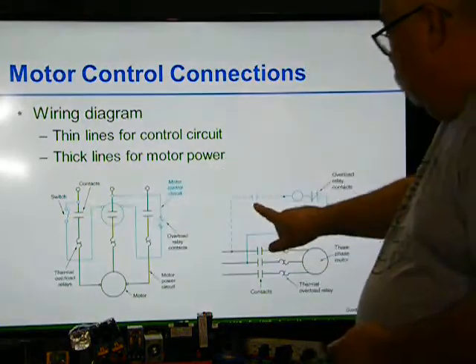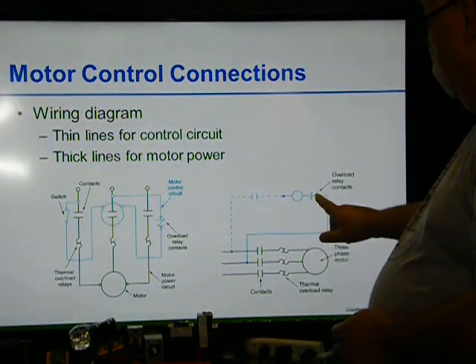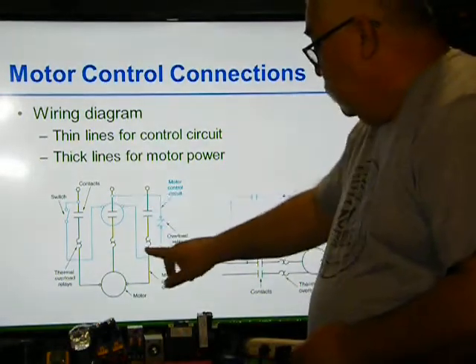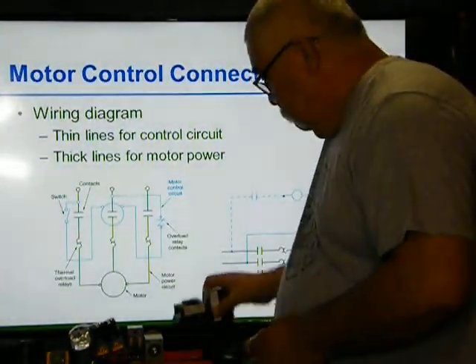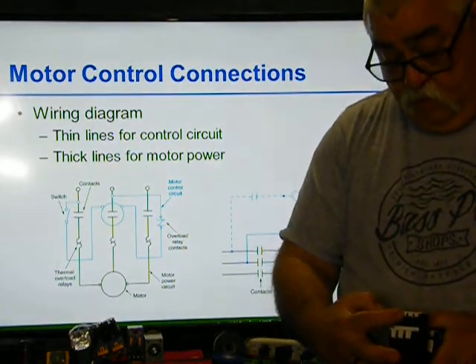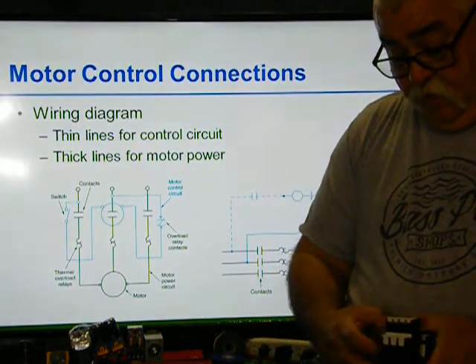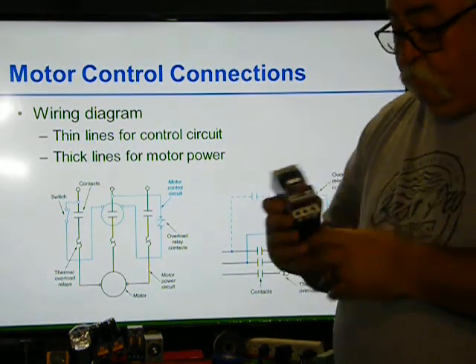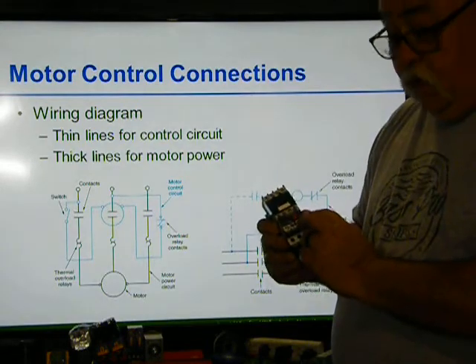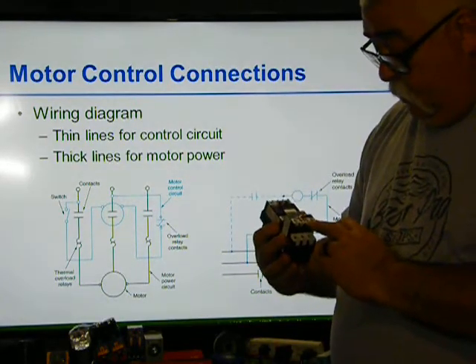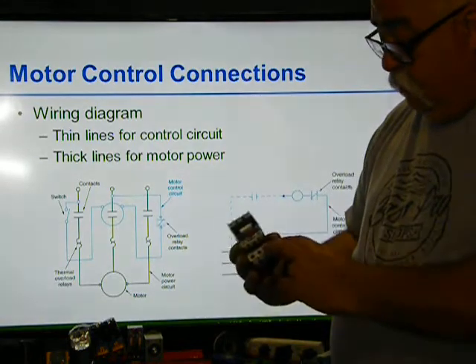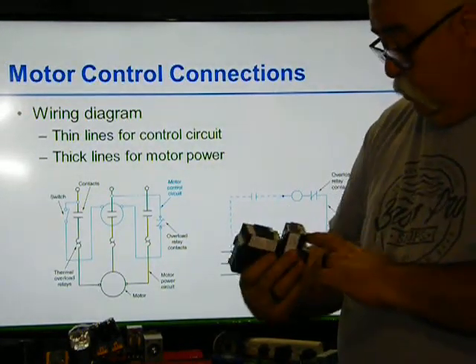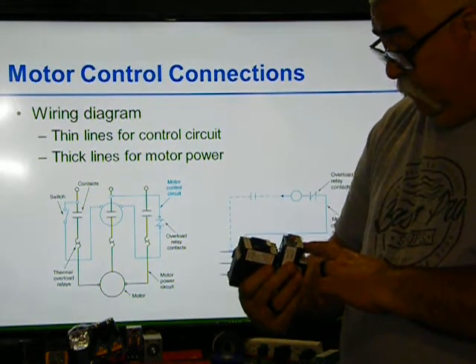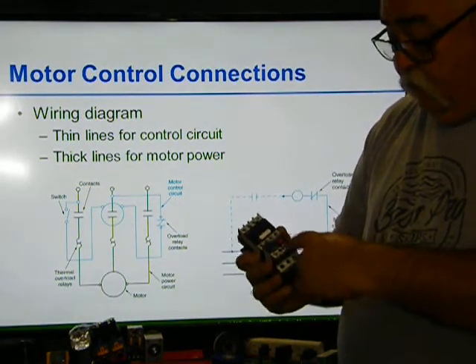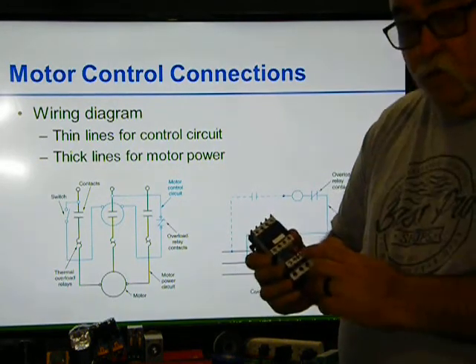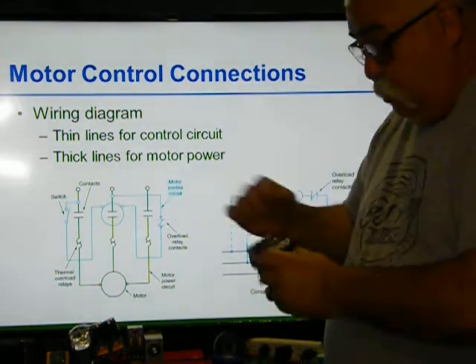Okay, here is my switch. The coil, and then this would be that other one. Okay, this one goes through the overloads. So this would come down to my overloads. I have my normally open and my normally closed, whichever one I want. It says NO, and I've got 2 screws and NC. Normally closed, normally open. So what it does, it comes off the coil and it comes to here. If I want it normally closed, I will tie into the 96 and 95. Okay, so I come into here. From here I go out that way. So this is always closed. So when you hit the switch, power goes out.